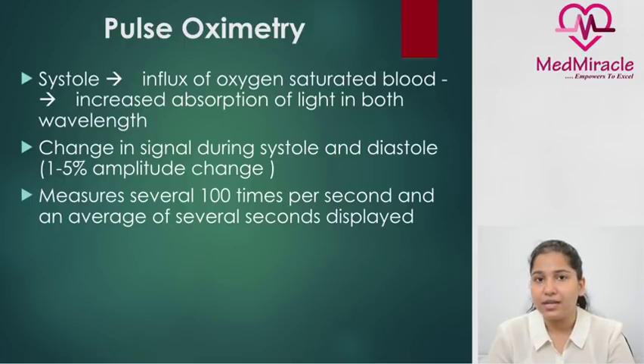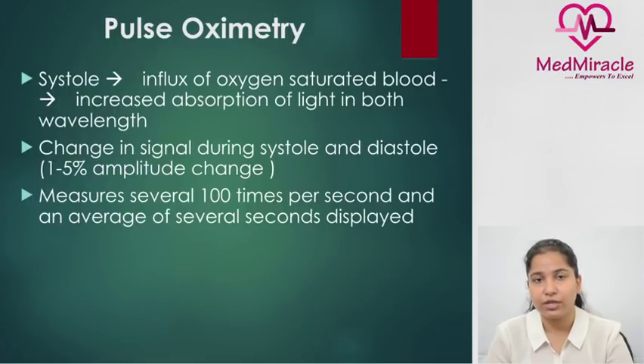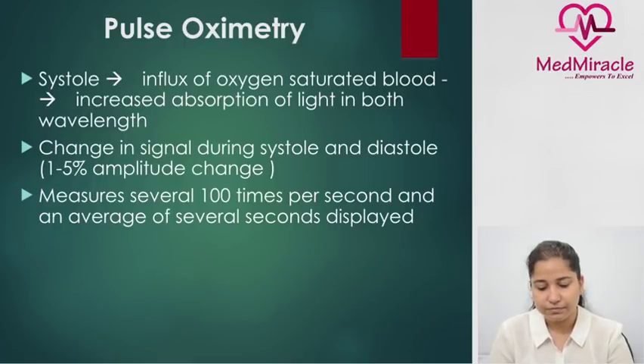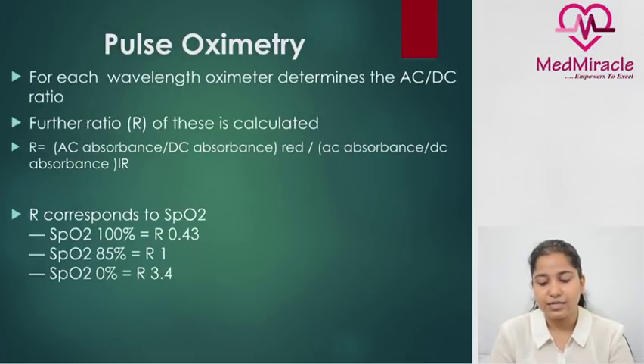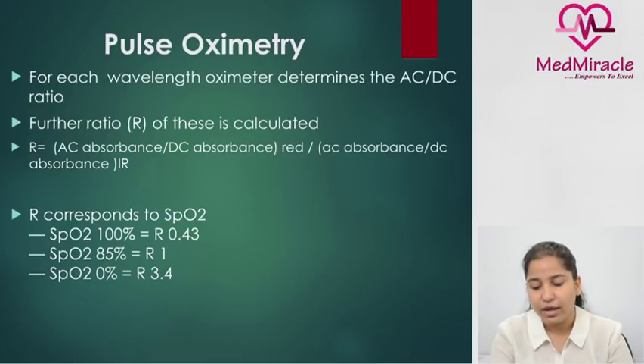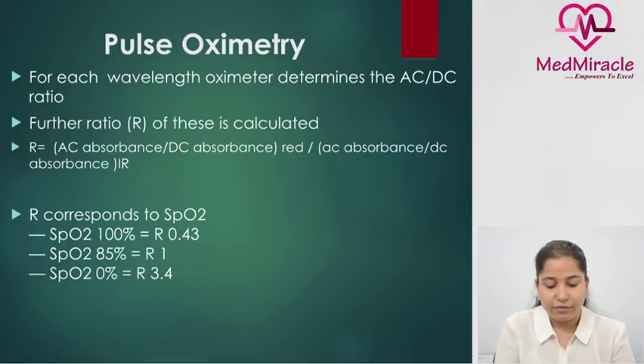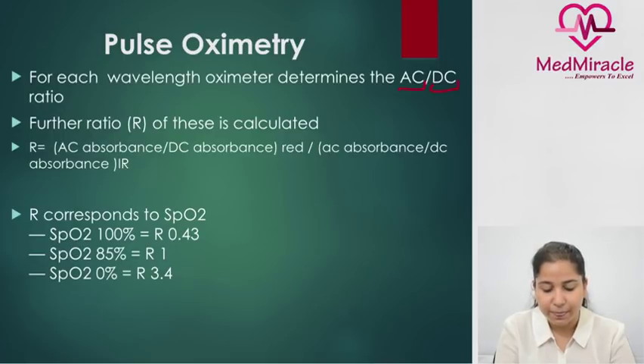The oximeter measures around 100 times per second and an average over several seconds is displayed on the monitor — which is why the SpO2 probe takes some time to display a value when first applied. For each wavelength, the oximeter determines the AC and DC ratio: AC is pulsatile blood flow and DC is non-pulsatile blood flow. When SpO2 is 100%, the ratio of red to infrared is 0.43, and when it is 85%, the ratio is 1.